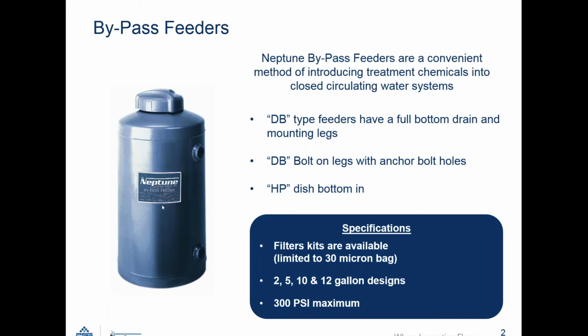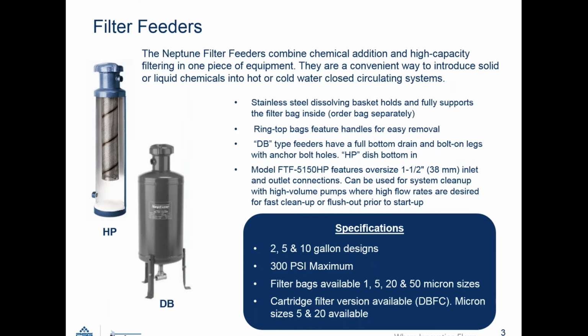The volumes that we have are 2, 5, 10, and 12 gallon designs. And the maximum pressure of the vessel is 300 PSI. The filter feeders are just like bypass feeders. They can introduce chemicals into the system through the top cap.